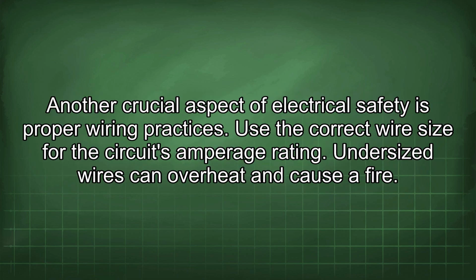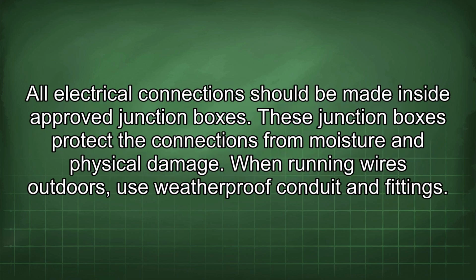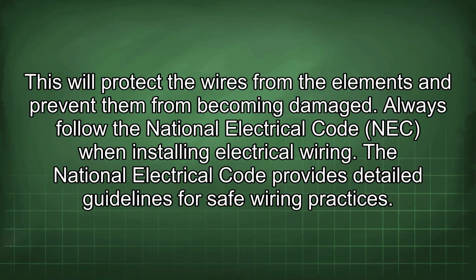Another crucial aspect of electrical safety is proper wiring practices. Use the correct wire size for the circuit's amperage rating. Undersized wires can overheat and cause a fire. All electrical connections should be made inside approved junction boxes. These junction boxes protect the connections from moisture and physical damage. When running wires outdoors, use weatherproof conduit and fittings. This will protect the wires from the elements and prevent them from becoming damaged.